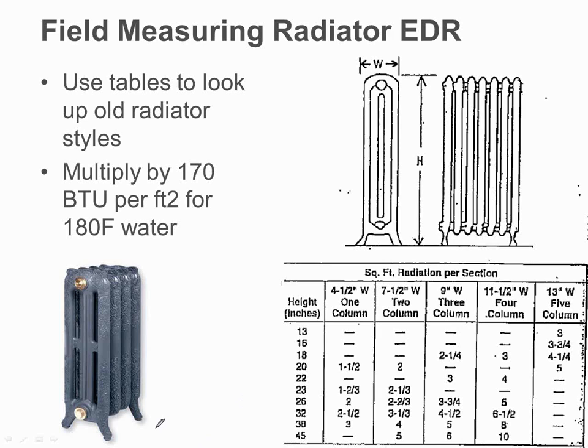A few years back, they did an experiment to see how close they were, and these guys were within about 3 to 4%. That was the old method. There is also a book out there called EDR. It's called Every Darn Radiator. You can get it on the web. Very, very good book. It's probably about 300 pages, and it shows all these radiators and gives you the square foot radiation, or EDR, numbers. What you're doing with a radiator, and here's where the tape measure comes in, is measuring the height.